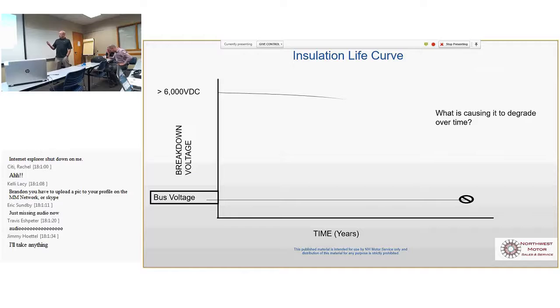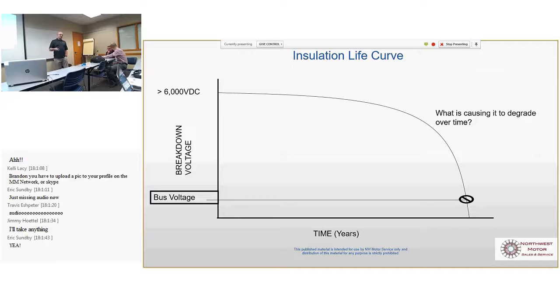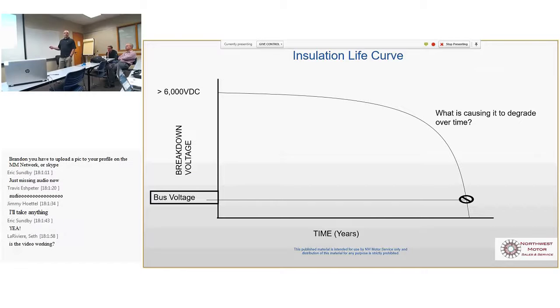So when it's new, like I said, it's 6,000 volts. Now, as the years go by, all the starts and stops, the heat, contamination, vibration, all that stuff put together is why it starts degrading over time. Eventually it can only withstand 5,000, 4,000, 3,000, 2,000, and you get down to bus voltage, and you start having a problem. That's when the thing's going to blow up on you.